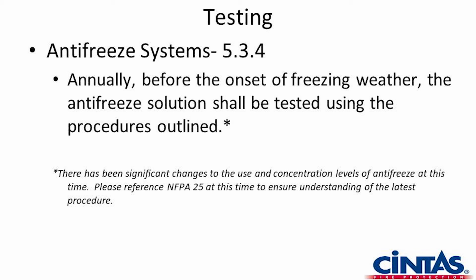and the city, and we followed the lines out, and it said that we had to be protected to 10 degrees, minus 10 degrees. When we tested that solution, we would go to the chart in NFPA 25 and see if the solution was good enough for the temperature that area would be subject to. And if it was, then it passed. And if it wasn't, it would be written as a deficiency. So a lot of things continuing to go on with antifreeze systems.